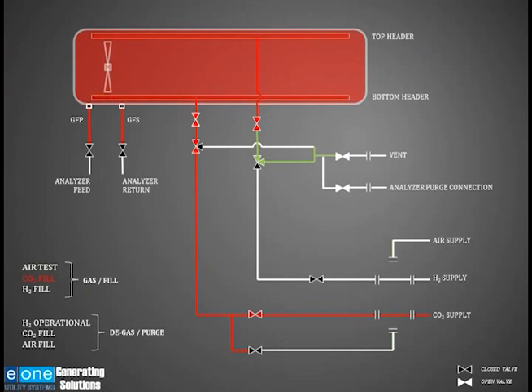Now you'll note that while we're doing this, we're analyzing our gas on the right-hand side, the analyzer purge connection, and that's where we're taking our purge sample. You'll also note that if I was monitoring my gas purity from my analyzer during normal operation, that's what I would see as soon as I started to put CO2 in that generator, because the sample is taken from the bottom of the generator. From taking it at the point of the vent, the generator has to be filled with CO2 before this analyzer recognizes that I have pure CO2 in the generator. That's a very important point. Now that I have CO2, an inert gas, in the generator, it's safe to put hydrogen into the generator.